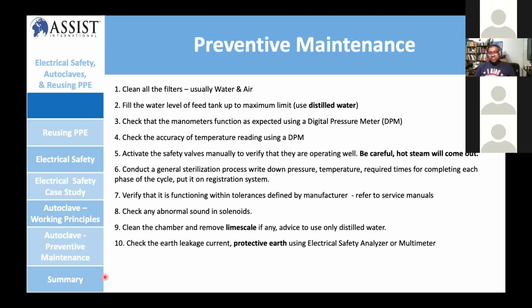Check that the manometer functions as expected using a digital pressure meter. You can do a pressurized test on that manometer to see whether it's working properly. At the same time, you can run the system and compare the pressure with the external connection. Check the accuracy of the temperature reading using the DPM, which has an external temperature probe. Activate the safety valve manually by pressing the check valve, and see whether it releases the pressure. Be careful, because hot steam will come out from there.